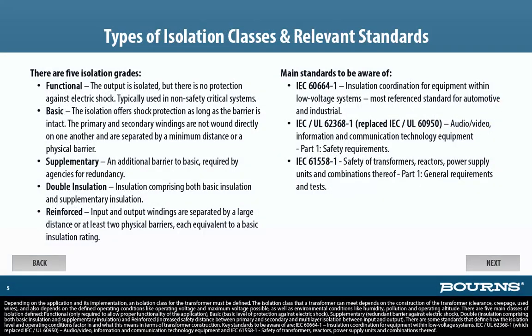Depending on the application and its implementation, an isolation class for the transformer must be defined. The isolation class that a transformer can meet depends on the construction of the transformer, such as clearance, creepage, and used wires, and also depends on the defined operating conditions like operating voltage and maximum voltage possible, as well as environmental conditions like humidity, pollution, and operating altitude.